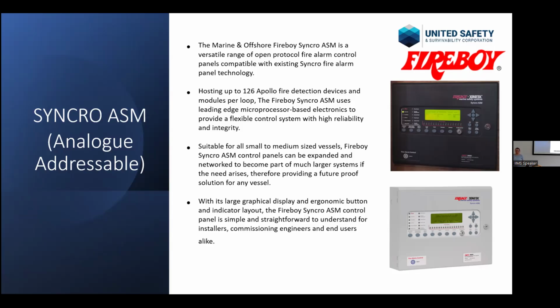The panel is quite large, so on some boats you might see it fitted somewhere in a cabinet, and they're only having a flush-mounted repeater panel somewhere on helm, or sometimes they use something like a Modbus output or RS485 to communicate directly with the automation systems, especially on pleasure yachts when they're trying to, you know, be sleek and not have a big metal box seen somewhere.